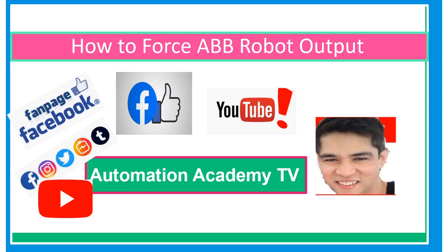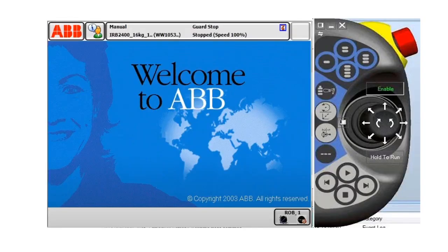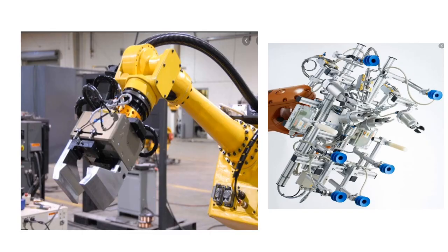Our topic for today is how to force an ABB robot output. Forcing or simulating an output is a very important procedure, especially if your tool is malfunctioning, because the clamp or gripper is not opening and the robot is in a tight space and you want the robot to move out of that device so that you can fix the tooling.